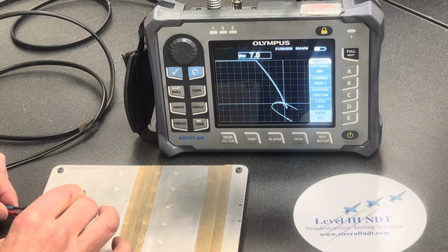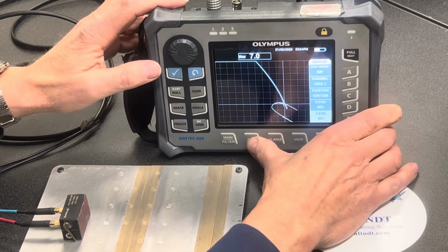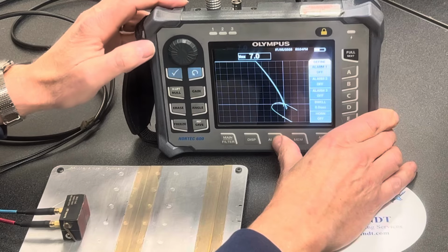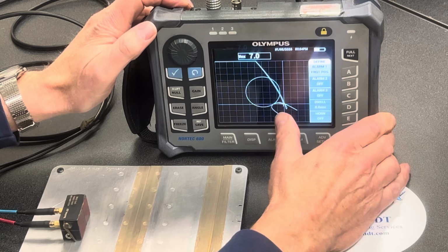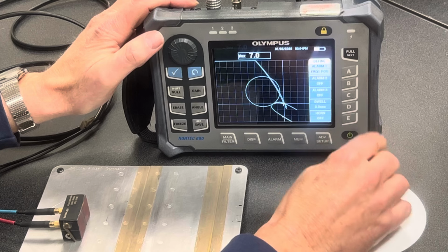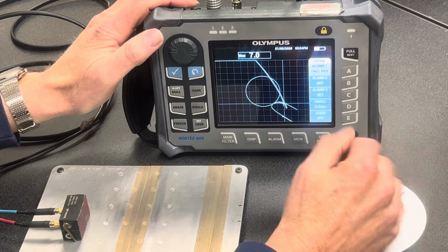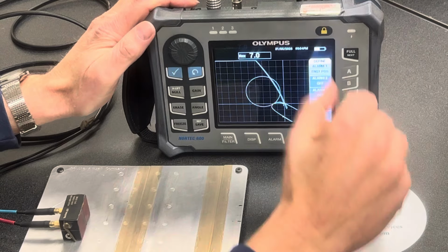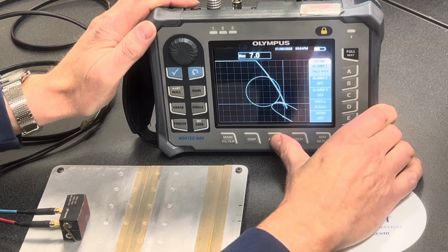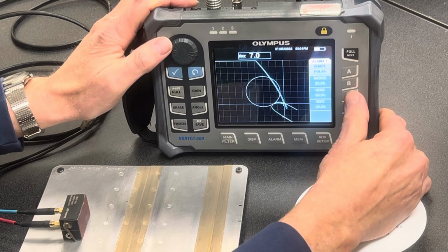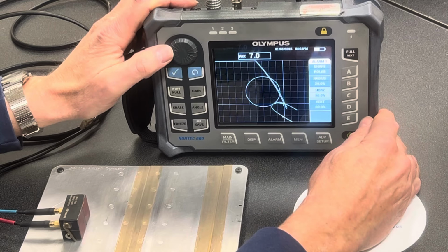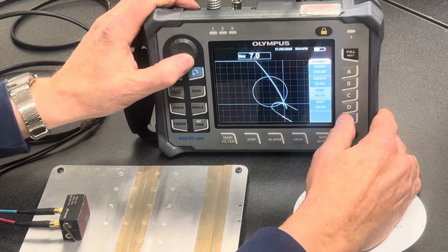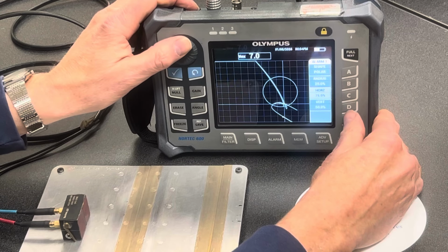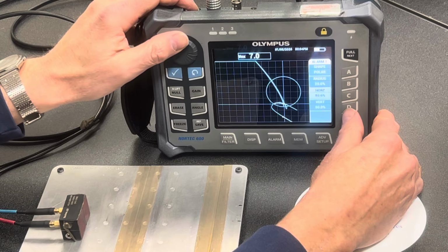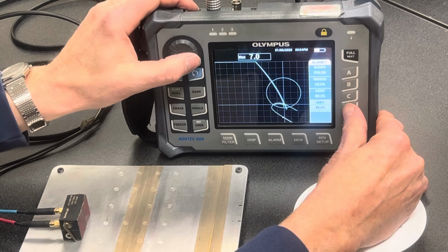And the next thing we're going to want to do is set an alarm. So we'll set an alarm. We'll set a polar alarm, and right now it has positive logic, so we only have the alarm if the dot goes into the box. The next thing that we need to do is set the alarm position. So we'll set it so it aligns with the null point position that we set, horizontal 80% and vertical 30%.